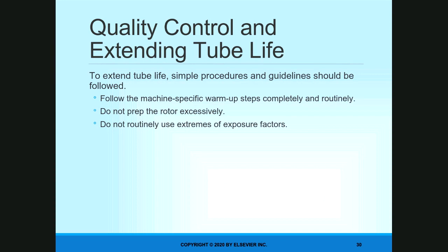Sometimes we sit on the rotor, but that actually shortens the tube life, so we have to be very careful. Ideally, you want to push the button all the way down so that you're not letting the rotor spin longer than necessary, because all that does is create extra heat in the X-ray tube, which is not good for the unit as far as lasting.